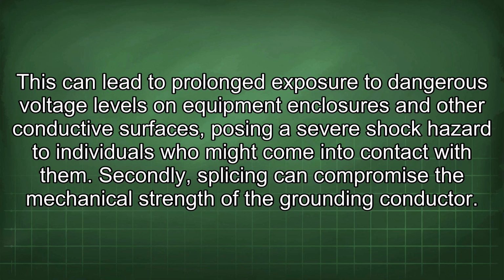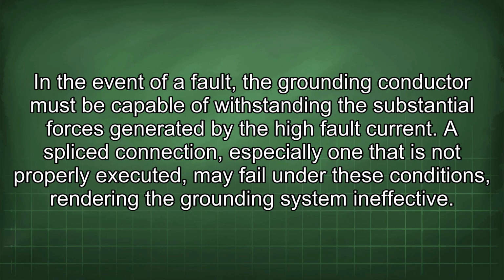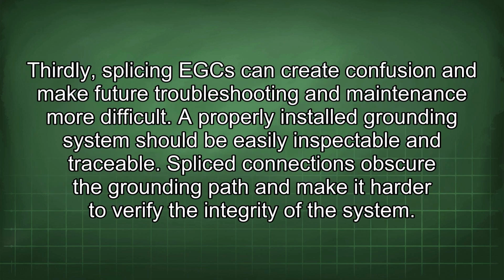Secondly, splicing can compromise the mechanical strength of the grounding conductor. In the event of a fault, the grounding conductor must be capable of withstanding the substantial forces generated by the high fault current. A splice connection, especially one that is not properly executed, may fail under these conditions, rendering the grounding system ineffective. Thirdly, splicing EGC can create confusion and make future troubleshooting and maintenance more difficult. A properly installed grounding system should be easily inspectable and traceable. Splice connections obscure the grounding path and make it harder to verify the integrity of the system.